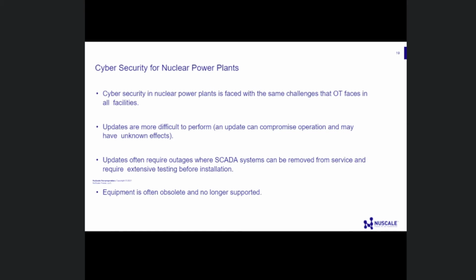Then you run into a problem of - I've done it where I've slow-clocked and all that kind of stuff - unfortunately, you can't test it enough as a private entity to do that. It's just, you have to test it way too much. So SCADA, systems for control and data acquisition - updates require outages. You got to shut the plant down, or part of the plant down, to get to that control equipment. Again, equipment's obsolete and off-supported. That is an OT problem everywhere - it's just a big deal to put in a control system. It's not just putting in a new computer.